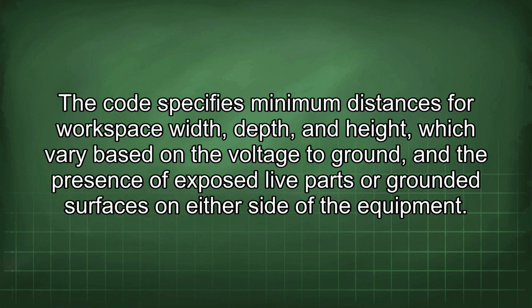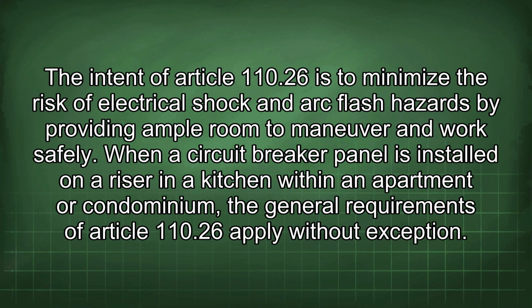The code specifies minimum distances for workspace width, depth, and height, which vary based on the voltage to ground and the presence of exposed live parts or grounded surfaces on either side of the equipment. The intent of Article 110.26 is to minimize the risk of electrical shock and arc flash hazards by providing ample room to maneuver and work safely.